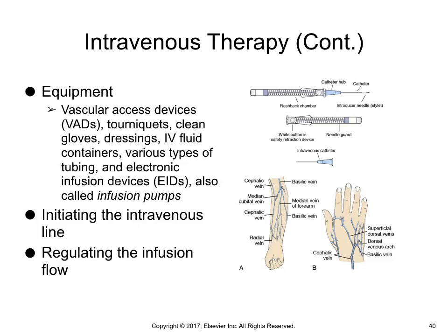Many infusion pumps have capabilities that allow for single and multiple solution infusions at different rates. Electronic detectors and alarms respond to air in the IV lines, occlusion, completion of infusion, high and low pressure, and low battery power. Regardless of the device in use, monitor the patient regularly to verify correct infusion of IV fluids.